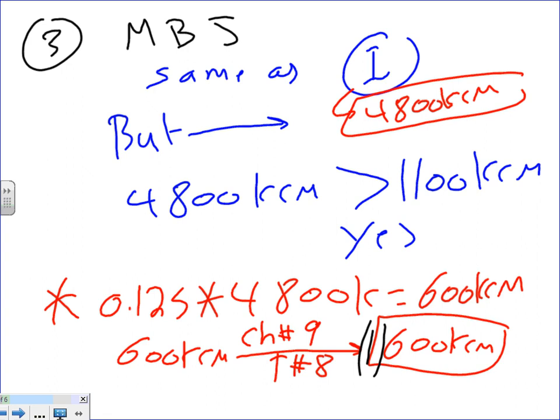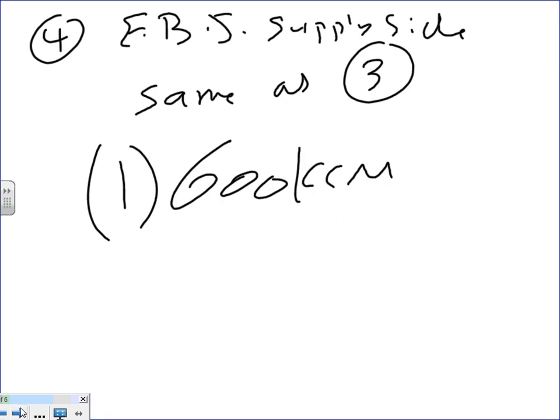Same as. The only difference, Spencer, is one of them is tying the neutral to the ground. The other one is tying the ground to the conduit. Or if it's metal conduit, then you don't need it? If it's a metal conduit coming from an open switch gear, the bottom is open. So you're coming from the ground and it's not attached to that's how most of these are. Switch gear sitting on a conduit. The conduit's not attached to the switch gear.